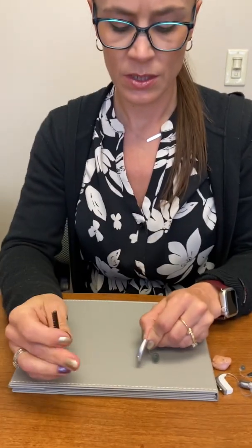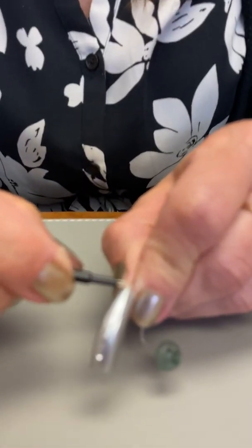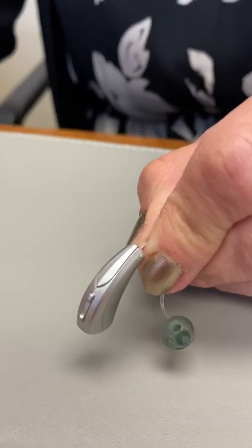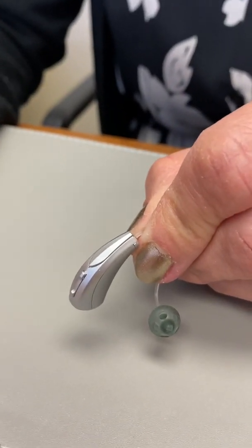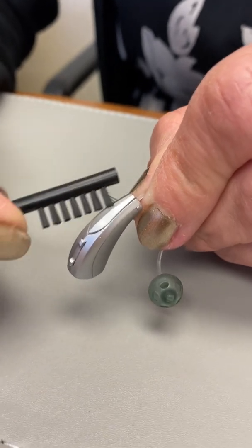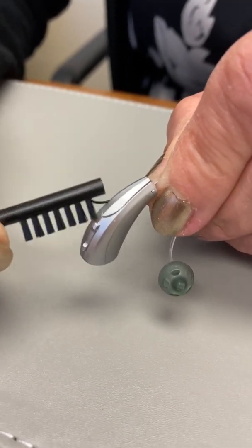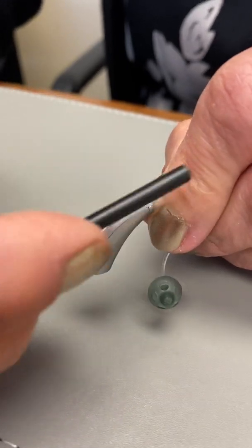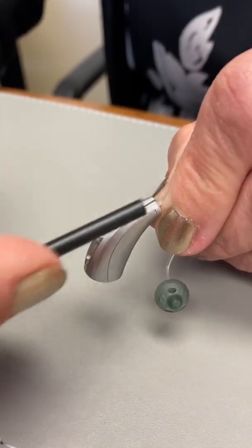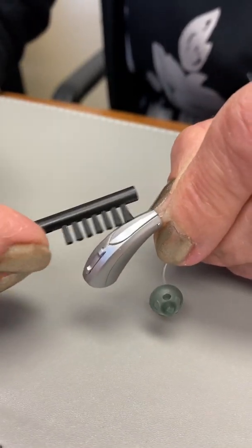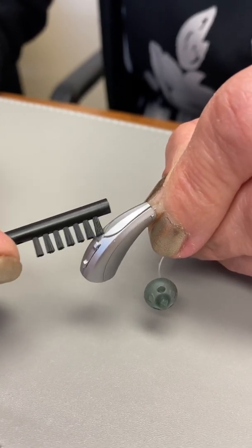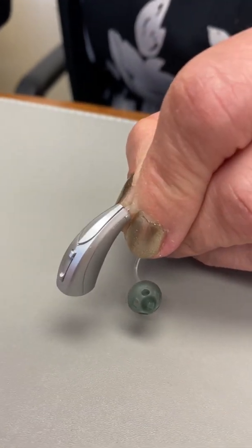Finally, I'm going to show you a Starkey device. These are a little bit different from the other two in that the microphones are actually recessed underneath this cover. So you're not going to see a true hole with these, but it's very important that you brush along the edge of this oval shape here to get any loose dirt, dust, or debris that may accumulate on the edge of the cover itself.